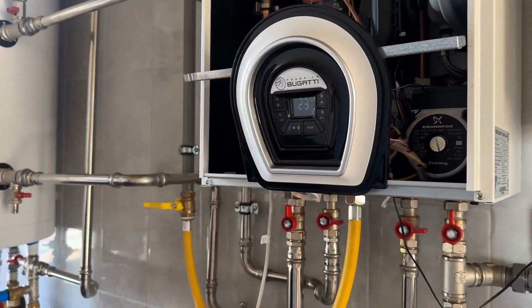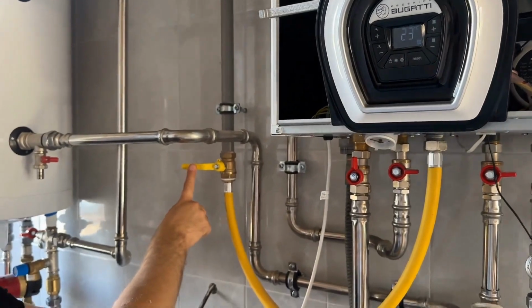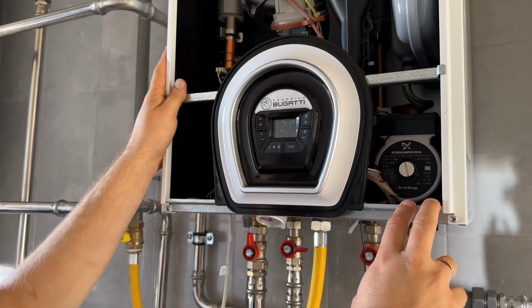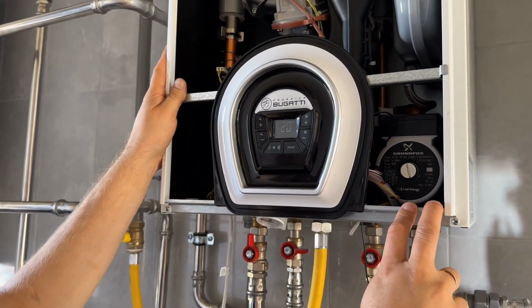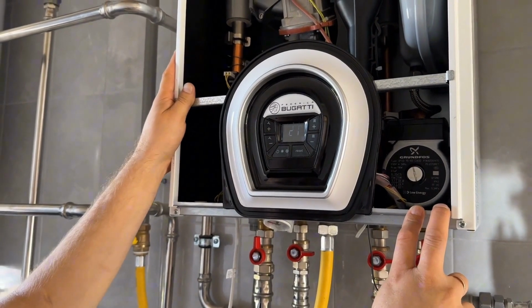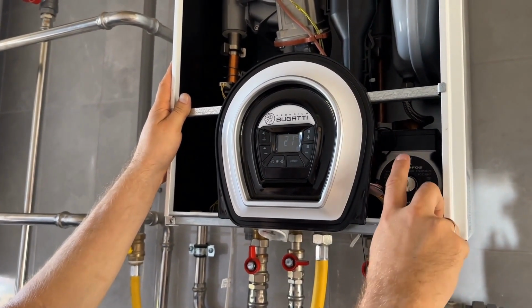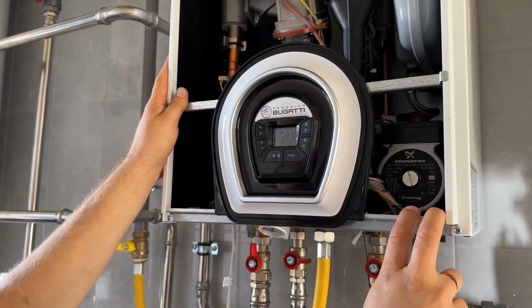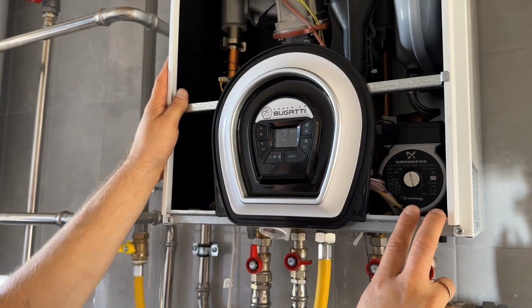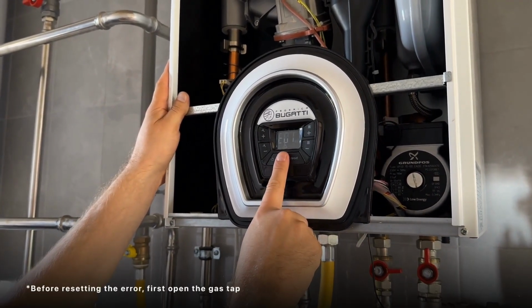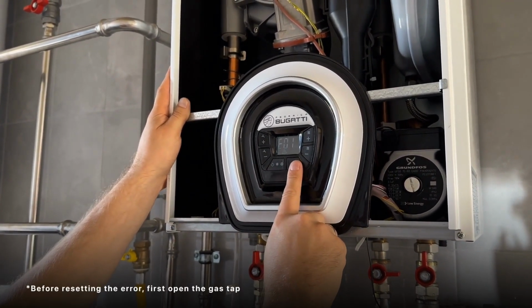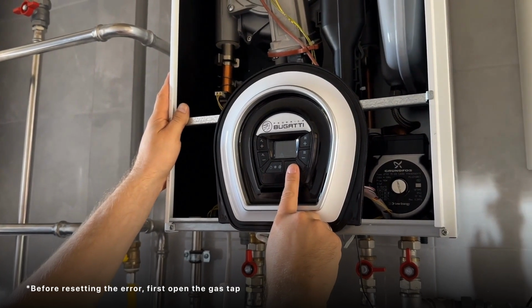I recommend performing the first startup of the boiler with the gas valve closed. While the boiler is attempting to start, we can ensure that there is circulation and that all the air has been removed through the air vent in the boiler and in the radiators. After 3 unsuccessful attempts to ignite, the boiler goes into error E01. It is also necessary to reset this error before the initial commissioning of the boiler.